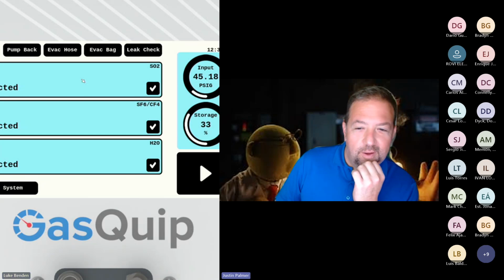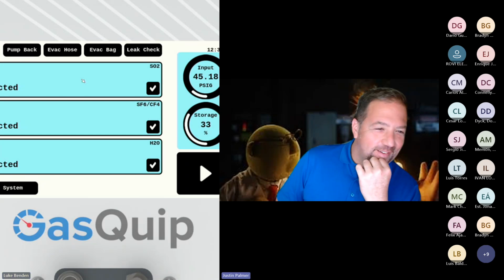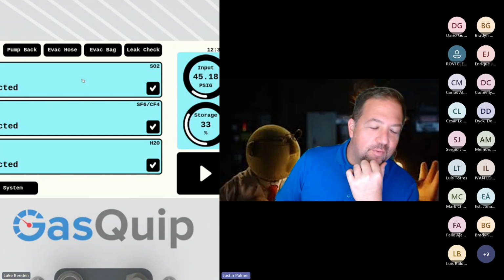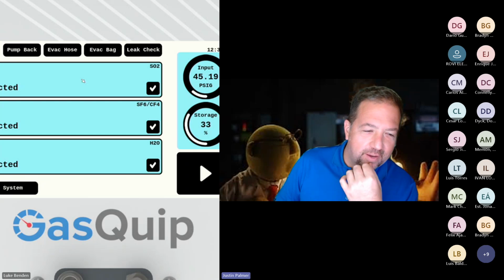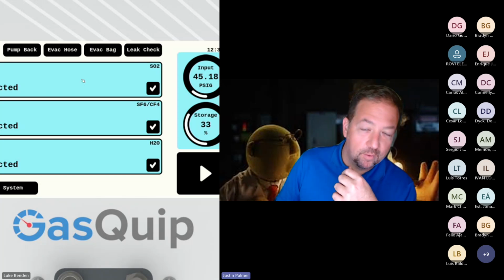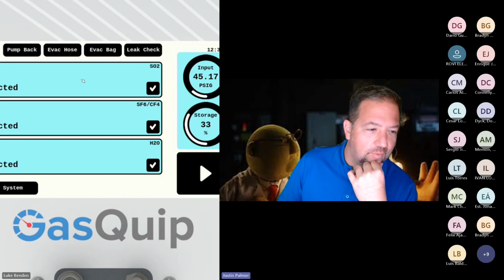Okay, and then oh hey Doug, the pressures on the device, it's from approximately 5 psi to 145 psi, and this is all gauge pressure for min and max pressures. That's for testing and for pumping, or pumping back is 145 as well, as Luke mentioned during the deal. So hopefully that covers that for you.